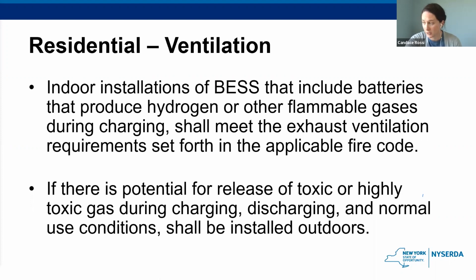So if there is potential for release of toxic or highly toxic gas during charging, discharging, and normal use conditions, then also the system should be installed outdoors. The exhaust fans will automatically turn on when these gases reach that 25% of the lower flammability limit of the room. And these ventilation fans will also be needed when a toxic gas is produced during normal charging or discharging. Yeah, so like I said previously, unlike conventional lead acid batteries, which produce hydrogen gas, the individual cells in lithium-ion batteries do not require ventilation, as they do not release toxic gas during normal operations.